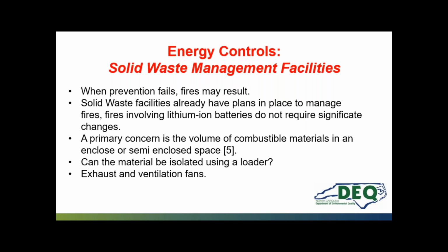Moving to solid waste management facilities, specifically transfer stations: when prevention fails, that means the battery was damaged at some point and now there's a fire. Solid waste facilities already have plans in place to manage fires, and fires involving lithium batteries don't require significant changes, because more than likely the fire concern is the volume of combustibles surrounding it. What we want to do is isolate the fire and isolate the combustible material around it.